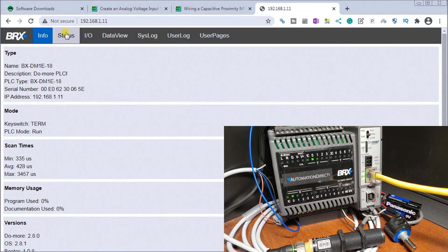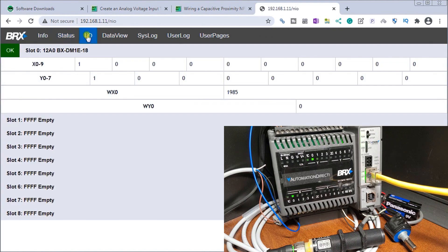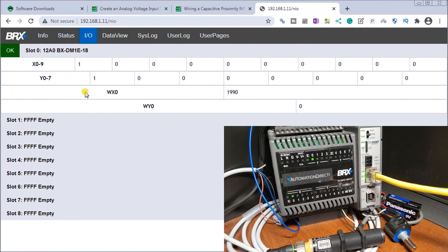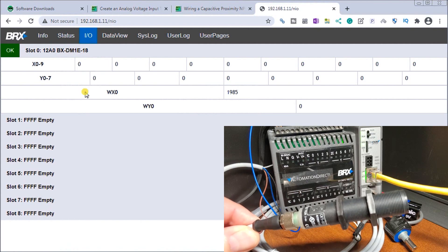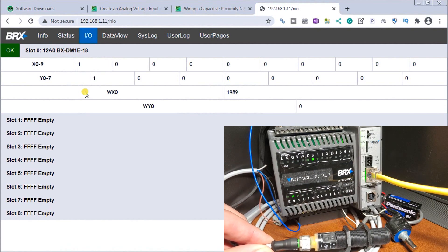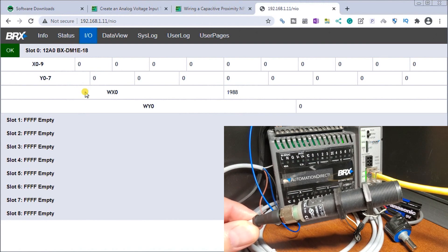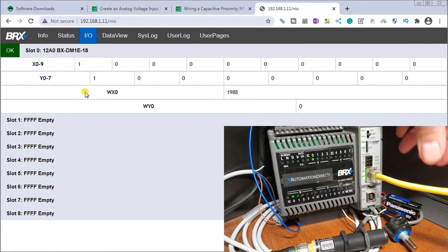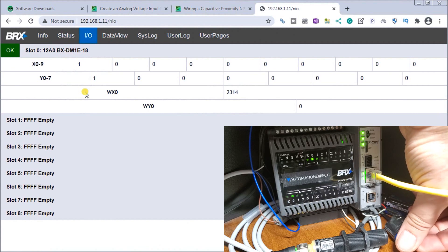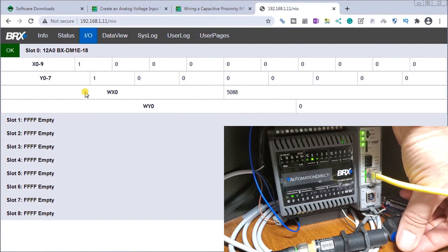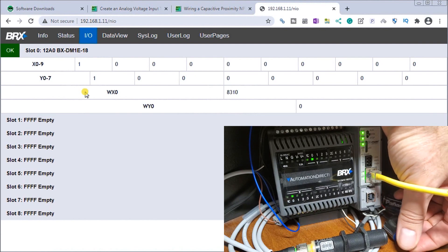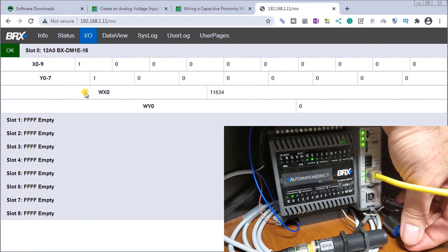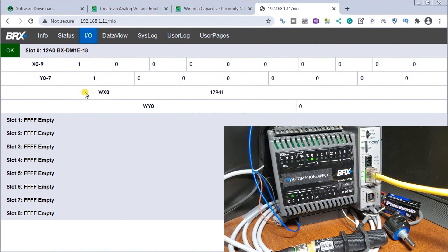Our next one would be our status. Here's our status for latest errors and warnings. Then we go into IO page. In the IO page you can see here that we have our analog input and we have our digital input and digital output. First of all let's lift that capacitive prox and turn it off. When we turn it off you'll see that they turn off. Turn it back on, they turn back on. So the website's actually quite responsive. Now let's take a look at our analog signal. We'll just turn that up and you can see how our analog is reading.